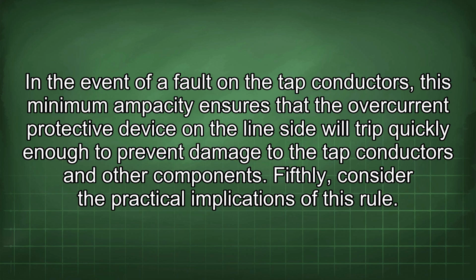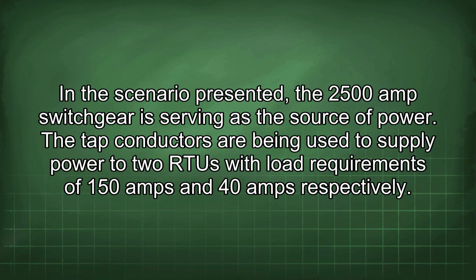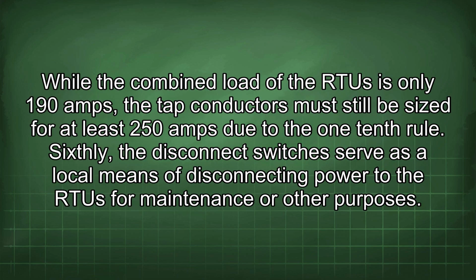Fifthly, consider the practical implications of this rule. In the scenario presented, the 2500 amp switchgear is serving as the source of power. The tap conductors are being used to supply power to two RTUs with load requirements of 150 amps and 40 amps respectively. While the combined load of the RTUs is only 190 amps, the tap conductors must still be sized for at least 250 amps due to the 1/10 rule.